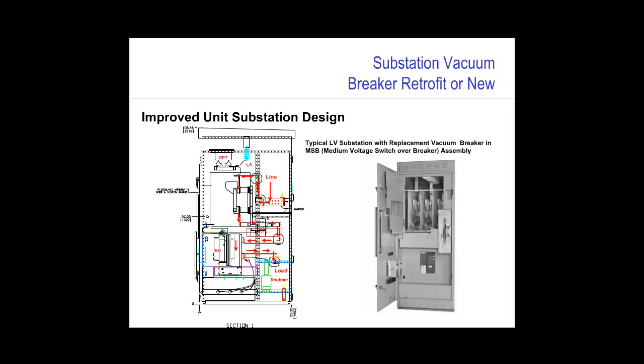I've shown on the left a section view of this MSB assembly, and if you follow the red lines from the incoming line in the upper right, you can see the terminations for the 15 kV power come in to the incoming bus, and you follow the arrows up and through the load break switch, and then back to the rear of the assembly through current transformers mounted on the bus, and then through the fixed mounted vacuum breaker and out to the load. You can also see in this assembly other items, including the snubber in the lower right, and in this case we have an application that included the requirement for a control power transformer at the upper section and also a lightning arrestor.